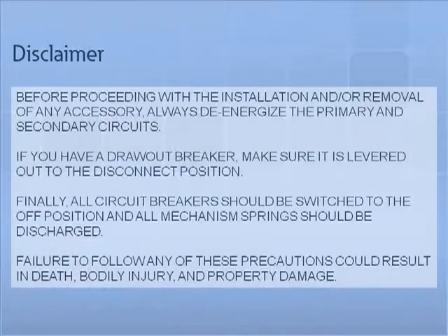Disclaimer: before proceeding with the installation and or removal of any accessory, always de-energize the primary and secondary circuits. If you have a drawout breaker, make sure it is levered out to the disconnect position. Finally, all circuit breakers should be switched to the off position, and all mechanism springs should be discharged. Failure to follow any of these precautions could result in death, bodily injury, and property damage.